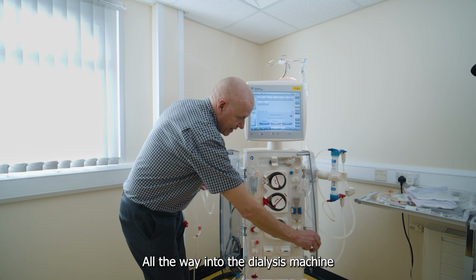In through the arterial line clamp, which clamps the line in the event of a problem with the machine. It'll close the blood line to stop any blood coming from your body if there's an alarm on the machine. Arterial pressure is measured at this point here. From here, the blood is taken through the arterial blood pump into the expansion chamber here. That pump will stop, and then this pump will start and push the blood through this line here and out to your dialyzer. The blood passes through the dialyzer where dialysis takes place.